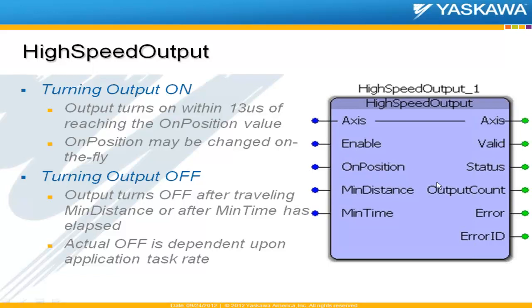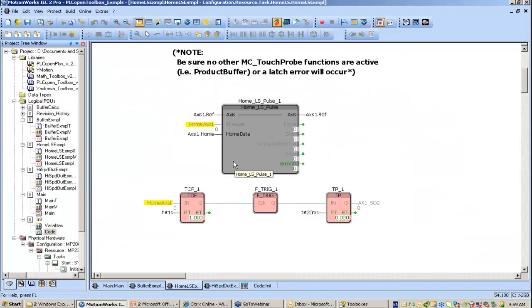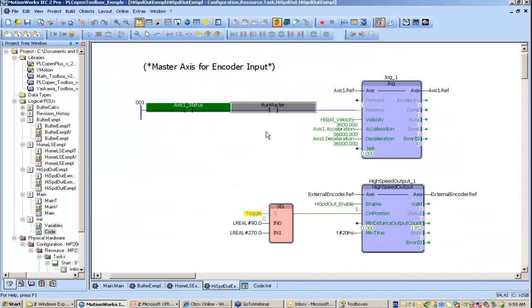To turn the output on, it will turn on within 13 microseconds of reaching the on-position value that has been set, and this on-position value may be changed on the fly. To turn it off, it will turn off after traveling either the minimum distance that's set or the minimum time that is set — one of those two inputs. The actual off is not high-speed; it is dependent upon the application task rate of where you've placed this function block.